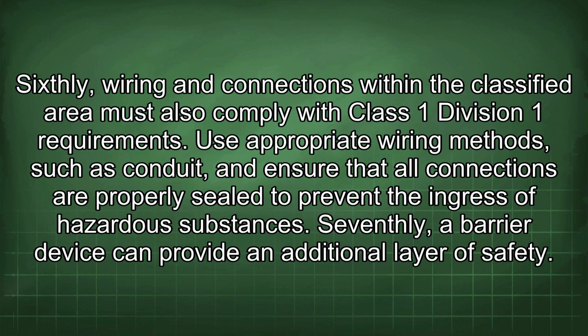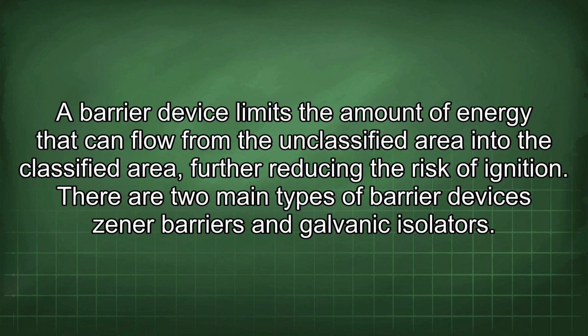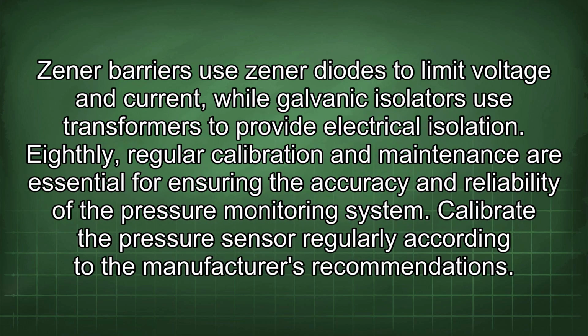Sixthly, wiring and connections within the classified area must also comply with Class 1 Division 1 requirements. Use appropriate wiring methods such as conduit, and ensure that all connections are properly sealed to prevent the ingress of hazardous substances. Seventhly, a barrier device can provide an additional layer of safety. A barrier device limits the amount of energy that can flow from the unclassified area into the classified area, further reducing the risk of ignition. There are two main types of barrier devices: Zener barriers and galvanic isolators. Zener barriers use Zener diodes to limit voltage and current, while galvanic isolators use transformers to provide electrical isolation.